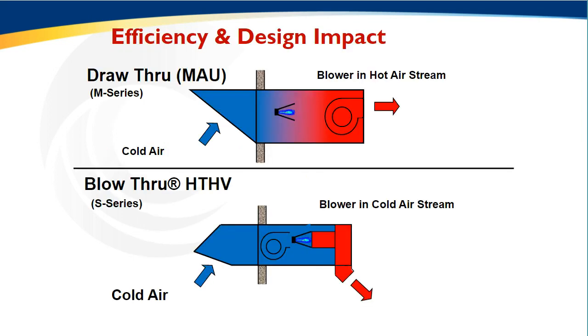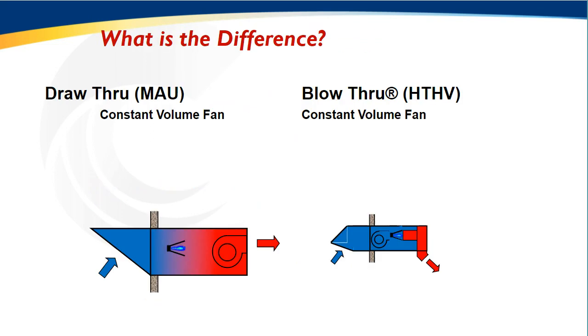So now I want to move into the energy efficiency side of it and talk a little more in detail about why high temperature and why blow-through becomes massively impactful from an energy efficiency perspective. So we're going to go into some granularity around the differences between HTHV and draw-through makeup air systems, particularly as it pertains to energy efficiency. So again, let's familiarize ourselves. The system on the top is your draw-through makeup air system, widely deployed in kitchen ventilation systems, paint booths, or other process exhaust systems. And on the bottom is our high-temperature heating and ventilation blow-through system, where the blower is in the cold air stream. So let's talk about what the differences are.